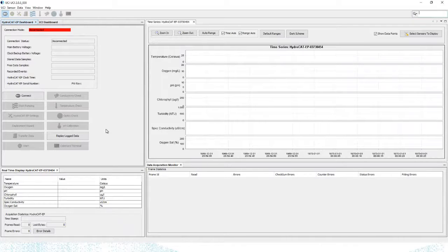Because I configured this for autonomous sampling and I set it to not transmit data in real time, once I finished the deployment wizard, it commanded the HydroCAT to go into standby mode, waiting for that date, I think December 15th, to start sampling. At that point, if we were to take this HydroCAT, put it in the closet, and then forget about it, it would start sampling on December 15th by itself and be writing that data to the memory. Alternatively, if you were to put it into the water, it would start sampling at that date. Because it goes into that standby mode, it disconnects from UCI. And so if we want to do anything else from within UCI, we can click on the connect button.